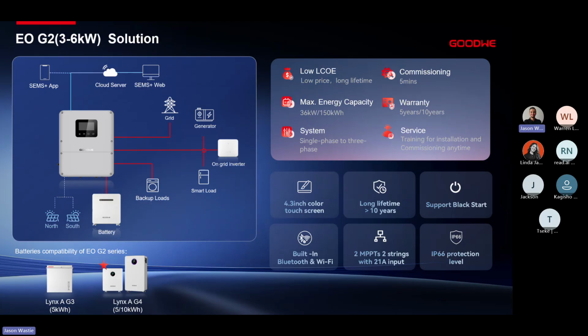One of the nice things about this unit that's quite different to all of our other units is that because it's our extremely compact unit, the communication dongle has been built into the system, meaning there is no external communication dongle that we need. There's a built-in Bluetooth and Wi-Fi chip, and we use it, one, to commission the unit, and two, to get it online for remote monitoring and configuration. There is a 4.3-inch color LCD touchscreen, for commissioning on site if we need to use it that way, and obviously for monitoring as well.